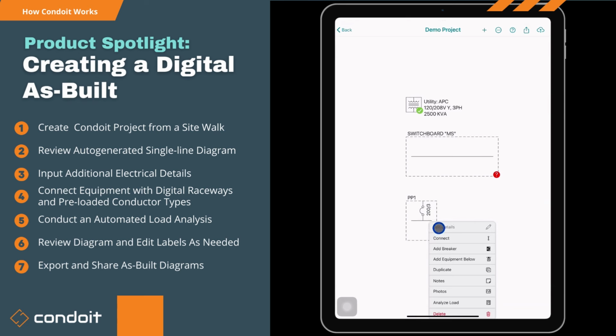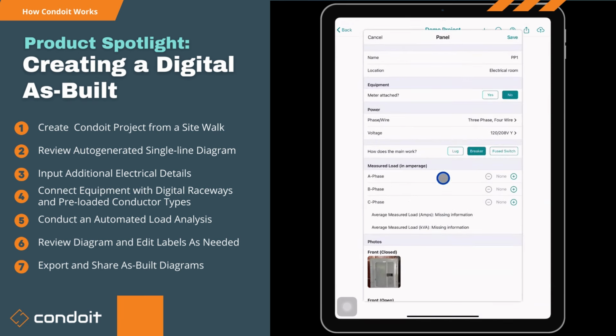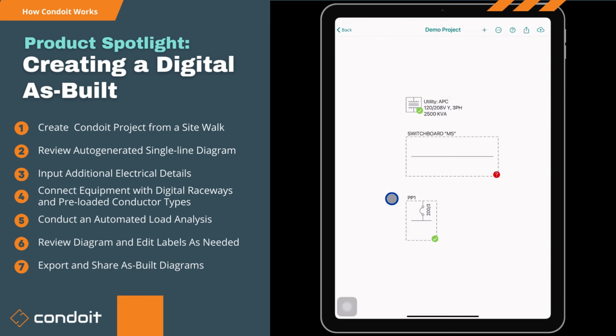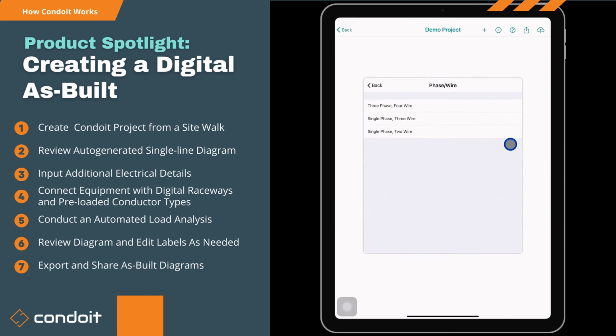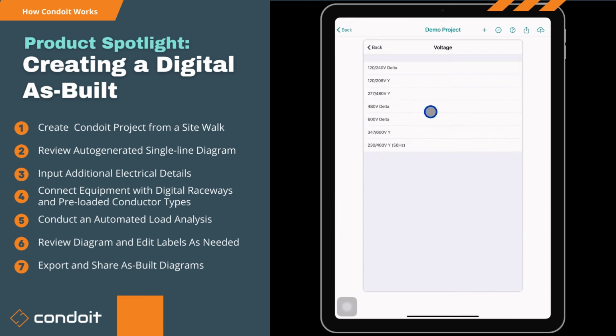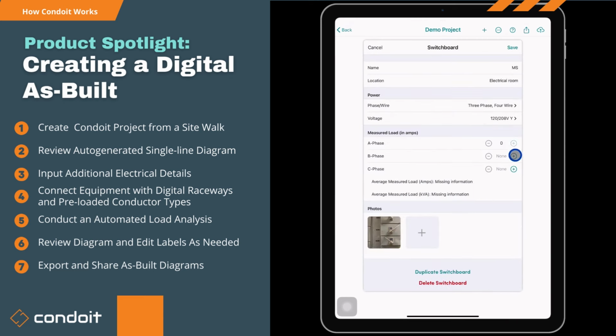Let's go back into this piece of equipment and you'll see that we're missing a measured load. So in this you can put in A, B, and C phase, say for instance if you have an eMon, Demon or something, and it'll start doing load calculations in kVA for you. So I'm going to hit save on there, and you'll see now we have everything we need for load analysis. But we're missing stuff on the switchboard. I'm going to go in here. I'm sure we need to set our phase wire in here as well. Say 3-phase, 4-wire, and then 120/208. We'll say that there's just a little bit of load on this one as well. Say 40 amps, nice balanced load on that piece of equipment.